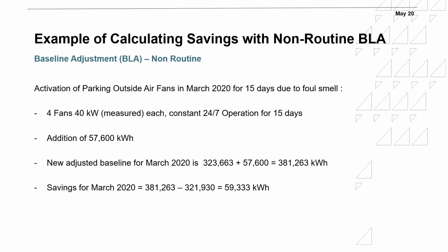In that particular building, there are 4 fans, 40 kilowatt each, operating 24/7 for 15 days in March. And normally these are off and only the exhaust fans are running, because the CO levels are never reaching a level where they need to turn on the fresh air fans. It's only one level of parking, so the exhaust fan was more than enough. However, during these 15 days, there was a foul smell in the basement due to some issue with the drainage, and they thought maybe they can add fresh air during that time to reduce the smell issues. So 15 days running 4 fans at 40 kilowatt.